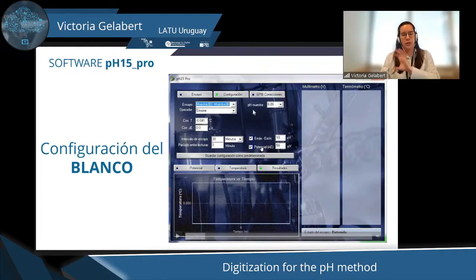Another condition I'm going to include here is that it's not going to be higher than 50 microvolts, because this will give me an idea of whether I rinsed out the cell correctly. It will also tell me how the electrodes are working, since they're platinum wires deposited with a small layer of platinum and palladium, which degrade over time or from contact with something else, and can become degraded or fall off.